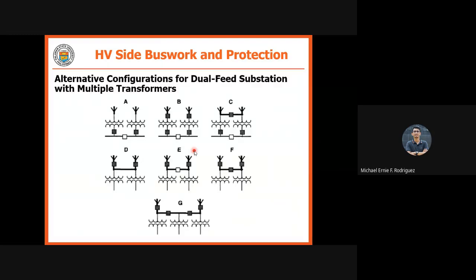We have alternative configurations for dual feed substation with multiple transformers. Okay, sa A, meron kang dalawang transformer, then you have protections on the low side. And then for letter B, meron kang protection on the high side. Okay. For letter C, ang naiba dito, you have a tiebreaker dito, which can be operated para pwede ma-transfer power from another line to another line, then going to your transformer. And then another one, letter D, wala siyang tie line, may line dito, pero walang tiebreaker. So, breaker lang on the lines. And then isang ito, merong normally open na breaker, ayan.